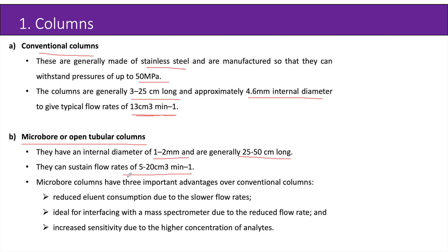Micro-bore columns have three important advantages over conventional columns: reduced eluent consumption due to slower flow rates, ideal for interfacing with a mass spectrometer due to the reduced flow rate, and increased sensitivity due to higher concentration of analytes.